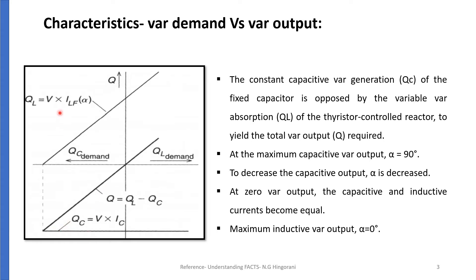QL is the Reactive Power Absorbed by the Inductor. It is given by QL = V × ILF(alpha). This fundamental current of TCR is a controllable quantity. By controlling this fundamental current we can control QL and hence we can control the system requirement of reactive power, i.e. Q = QL minus QC. QC is a fixed value whereas QL is a variable value. QL is varied in such a way that the required Q is attained.